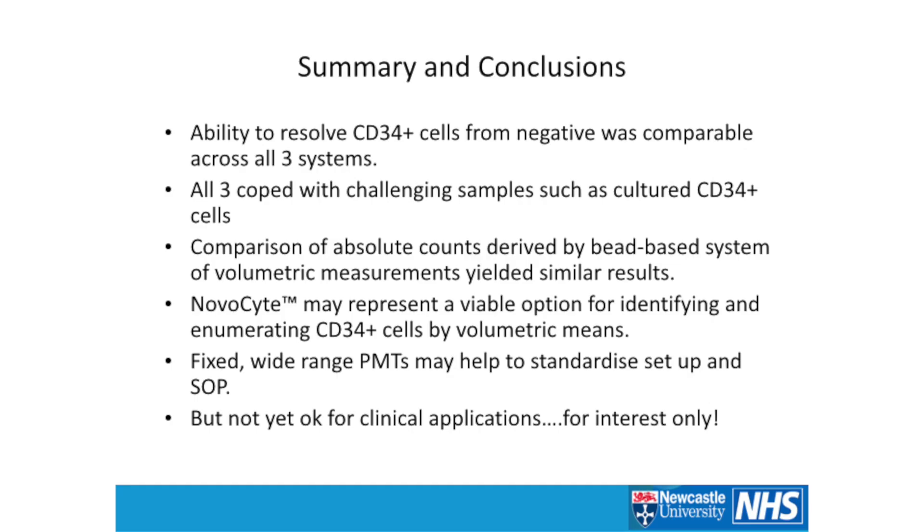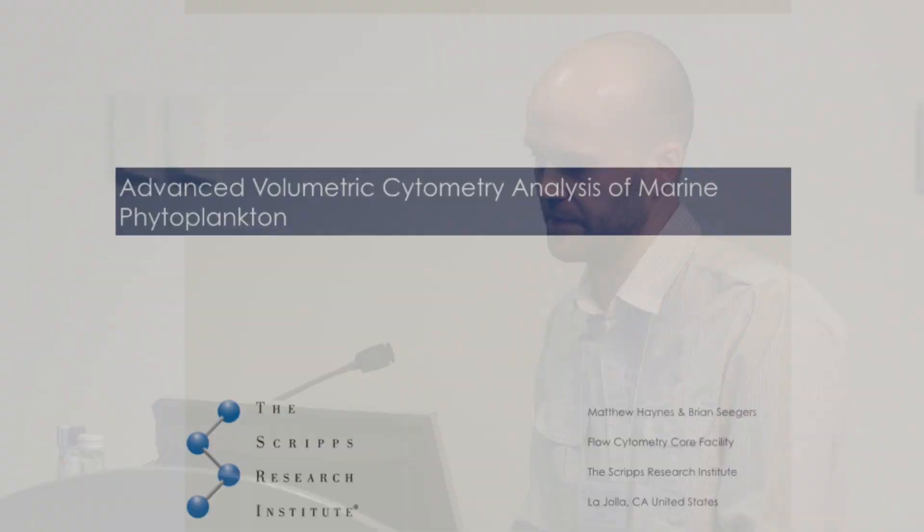To summarize: the ability to resolve CD34-positive cells from negative was comparable across the three systems. All three cope very well with more challenging cultured samples. The absolute counts derived by bead-based and volumetric systems were pretty much similar. The NovoCyte may represent a viable option for identifying and enumerating CD34-positive cells volumetrically, and the fixed wide-range PMTs would help if it ever goes down a clinical route — regulators like having fewer things to standardize and change. But this is very much for interest only. Thank you.